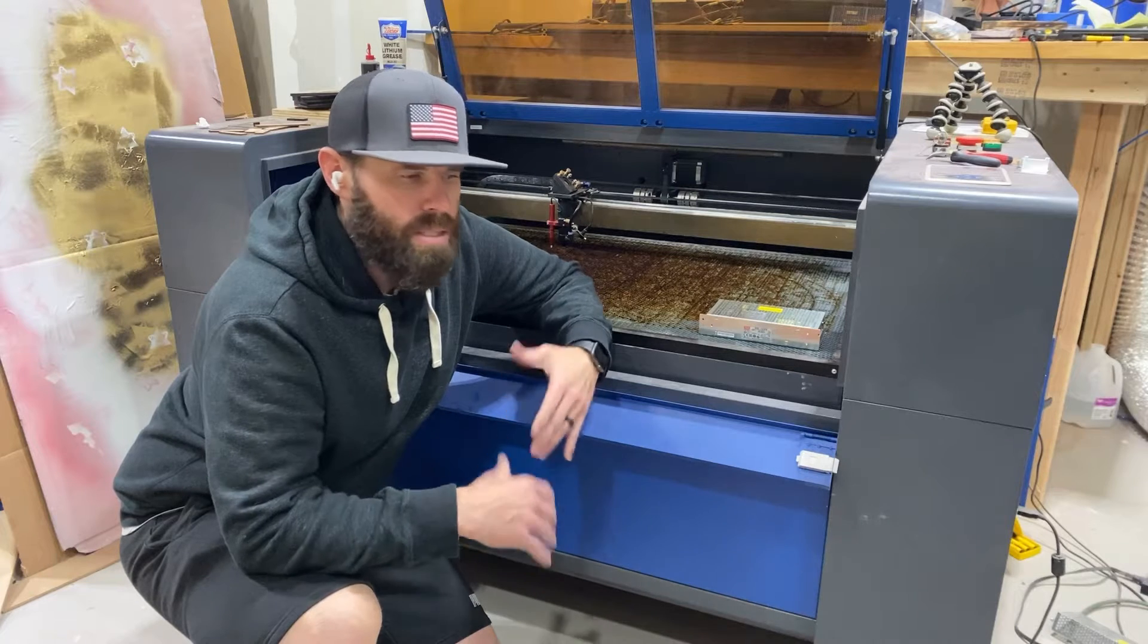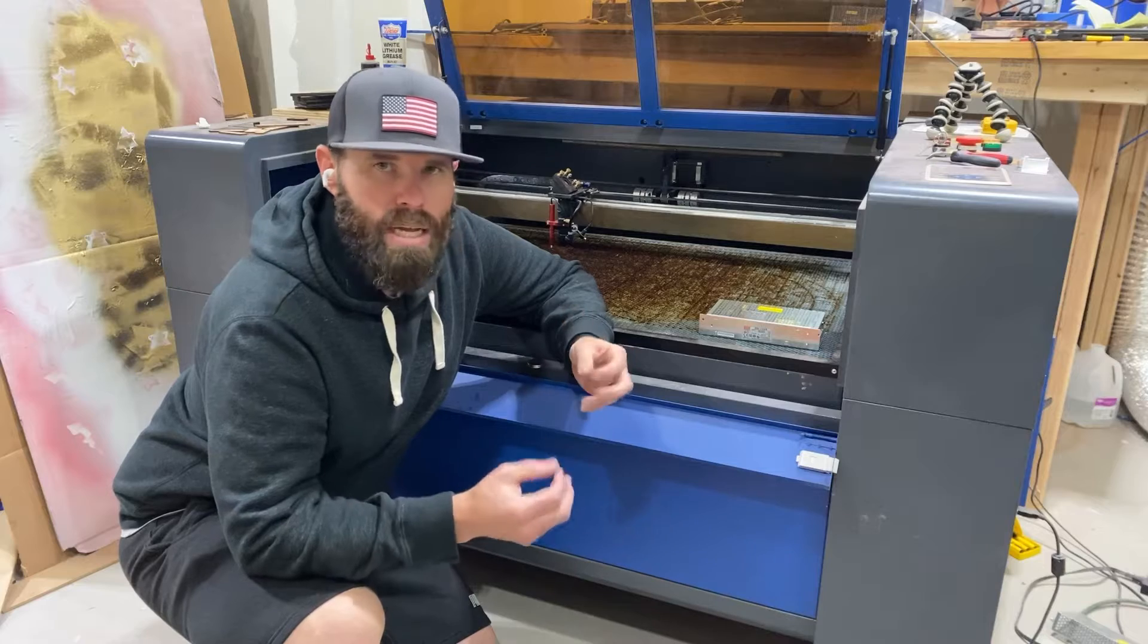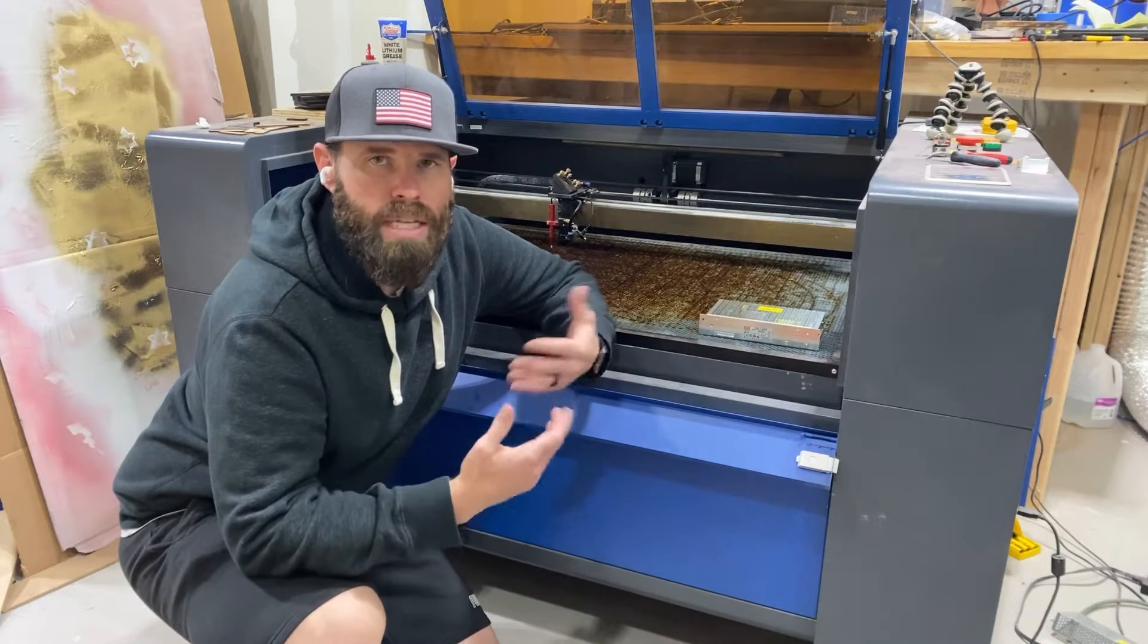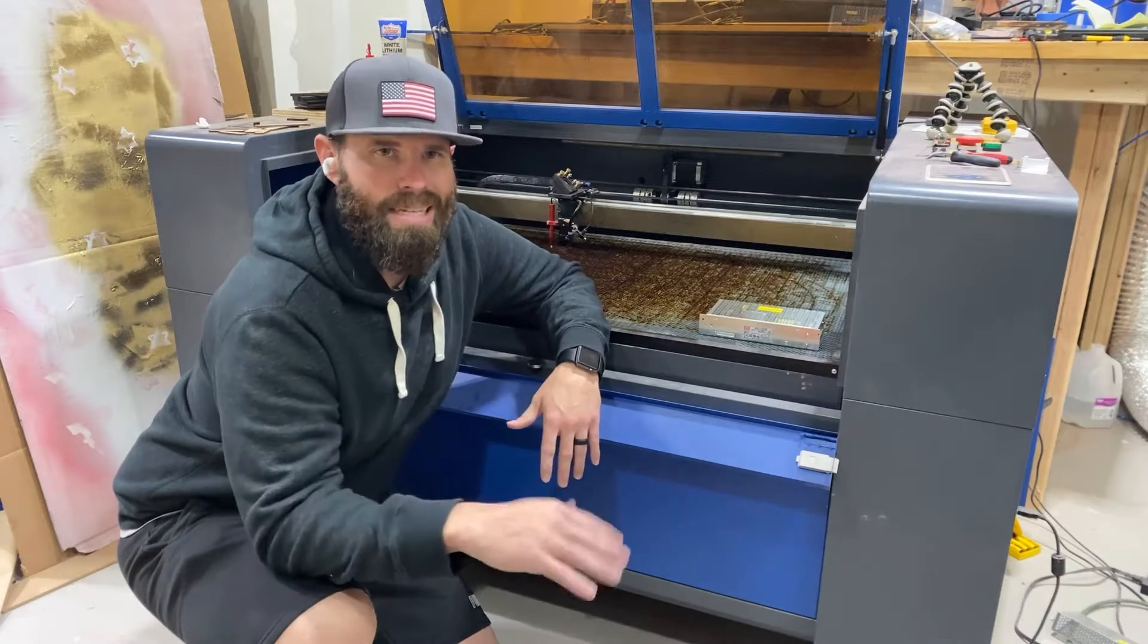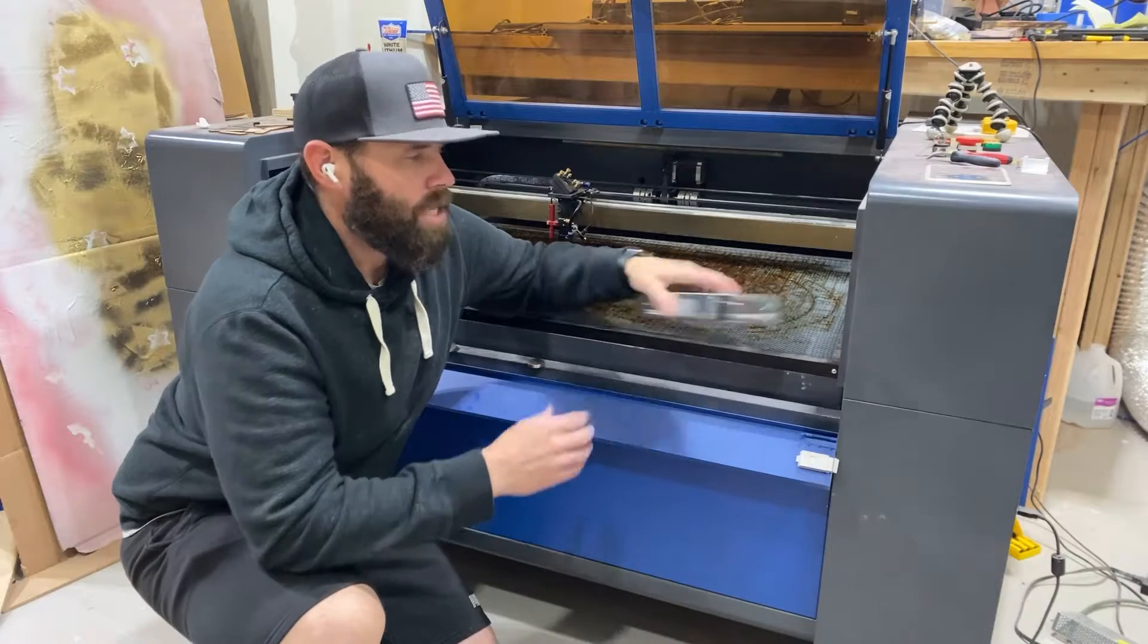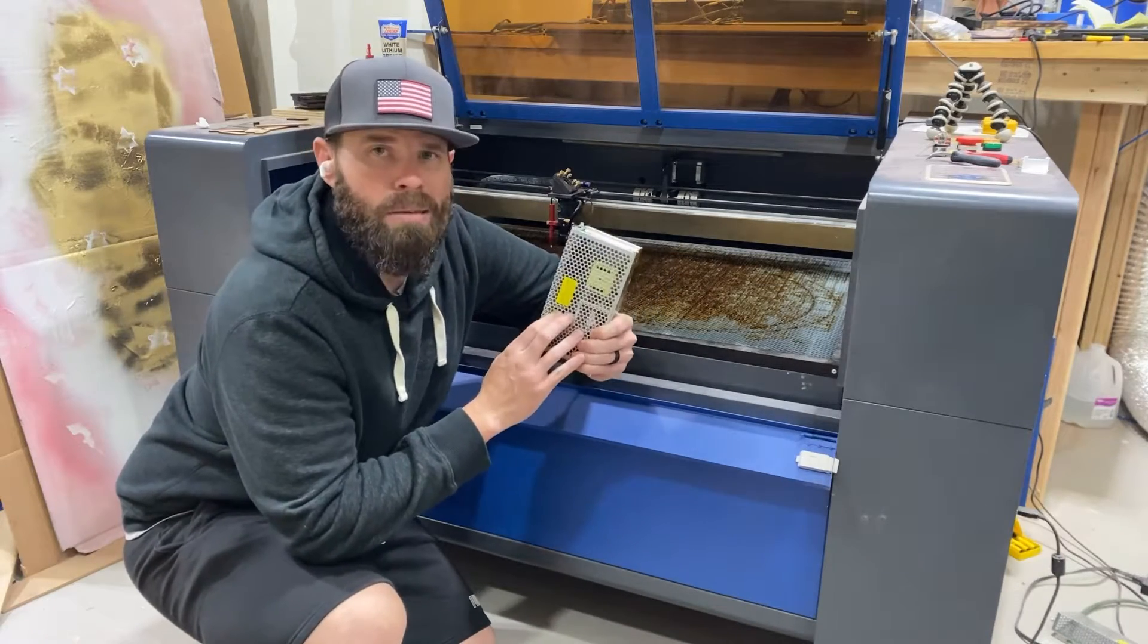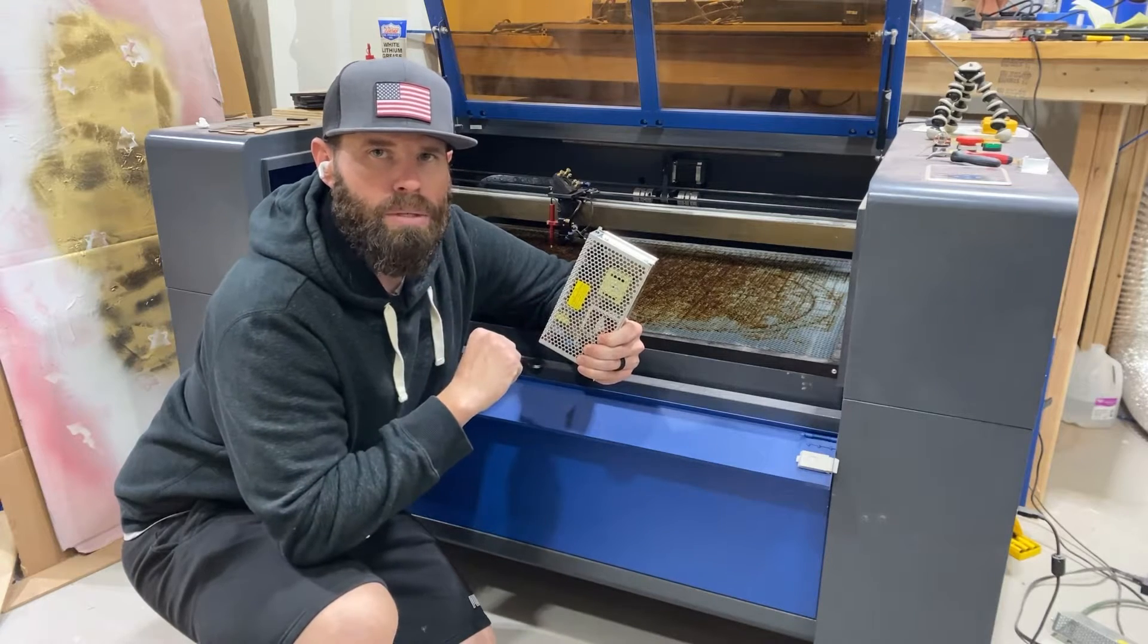I was sitting at the machine watching it do its work and all of a sudden saw some flickering, had some lights turning off, sensors going off and all of a sudden machine died. Come to find out, got looking around and found out that my 24 volt power supply had gone out. So that's what we're going to talk about now and I'm going to run you through how to replace yours.